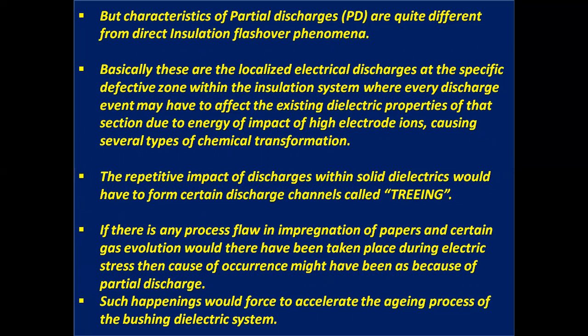Basically, these are localized electrical discharges at a specific defective zone within the insulation system, where every discharge event may affect the existing dielectric properties of that section due to the impact energy of high energy electrons or ions, causing several types of chemical transformation.